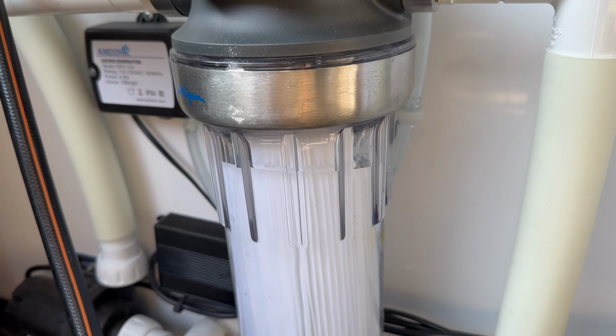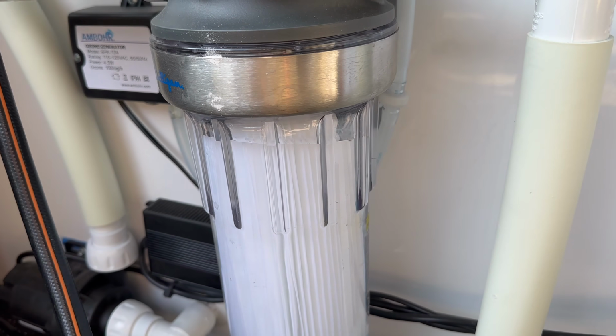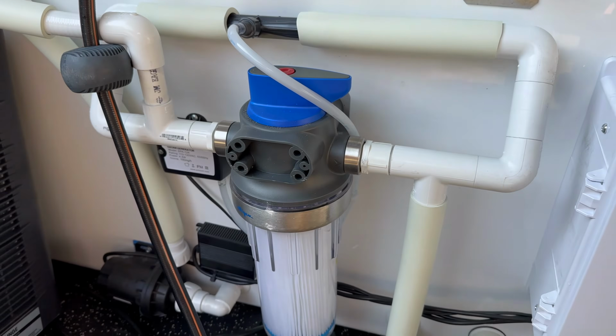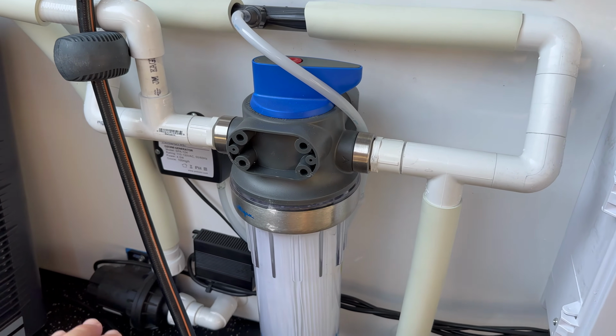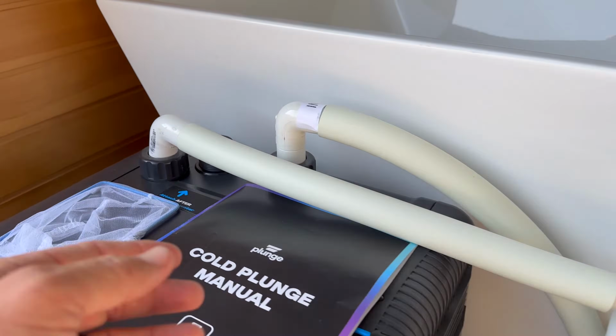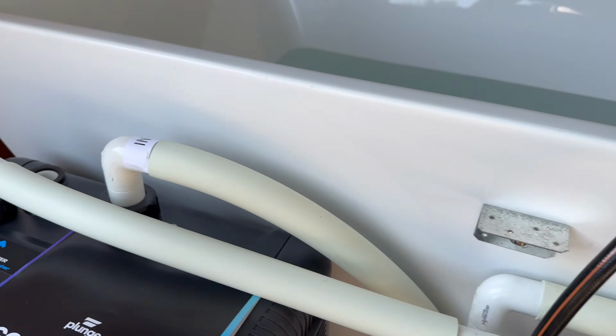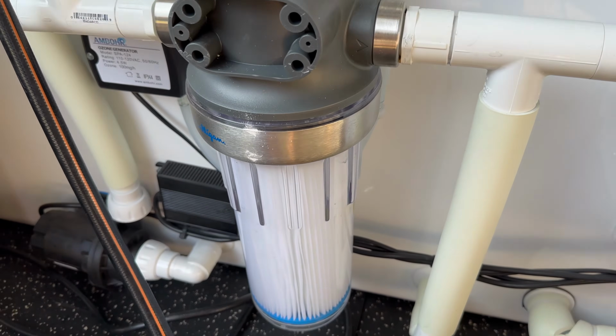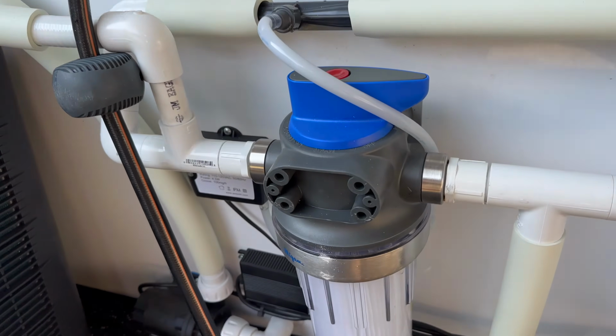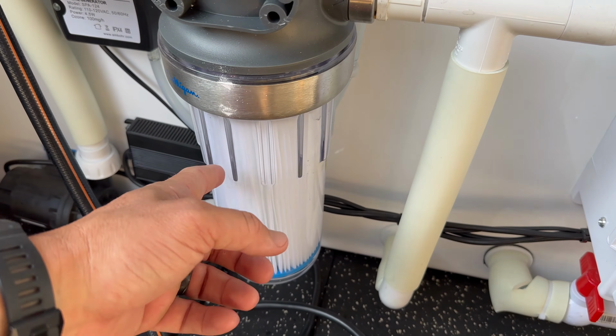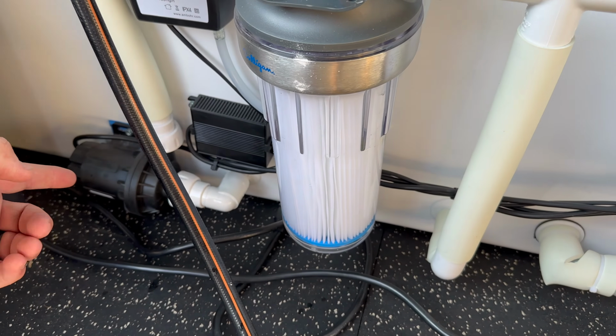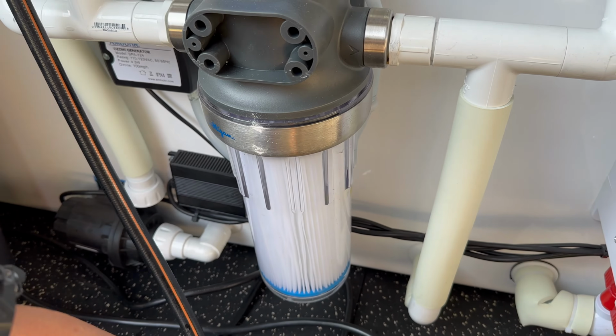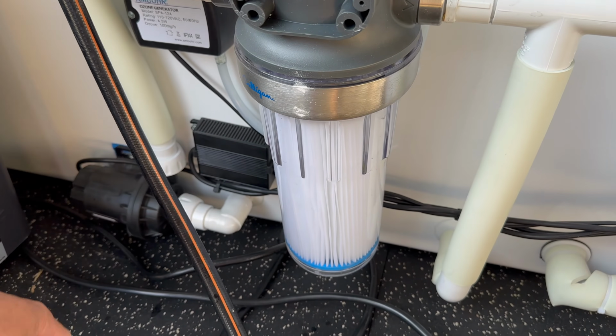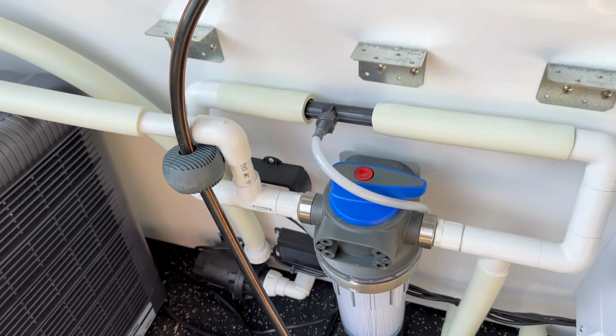You can tell when you get to that halfway point because the filter actually fills itself up - this is a great design. The gravity is feeding in, and when you leave this open it lets the air travel out and the water travel in. That's why you don't want to put this on until it's halfway full, because it helps with the water purging. Everything's full of water, so once the pump turns on, it can just send the water right on through. It keeps the health of your pump good, and the health of your chiller good too. I totally love that design.